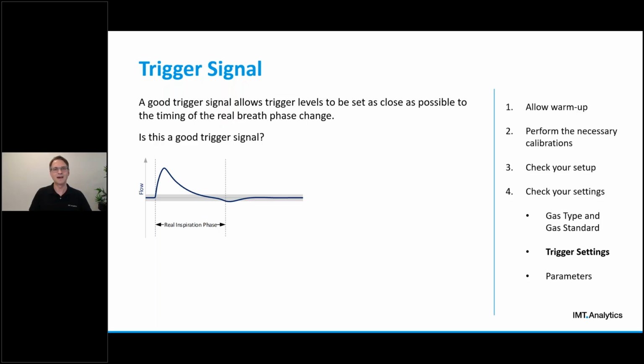Let's have a look at some example signals here and judge their qualification as a good trigger signal. What you can see here on the screen is a first example. The dashed vertical lines, the gray ones, indicate the real start and end of an inspiration phase. So this is where we would ideally want the trigger levels set in our gas flow analyzer. The gray area around the zero flow line indicates an area where we don't want to have our trigger levels, as a little bit of signal noise could create some false triggering. So we want to keep it a little bit higher or lower, not in that gray area.